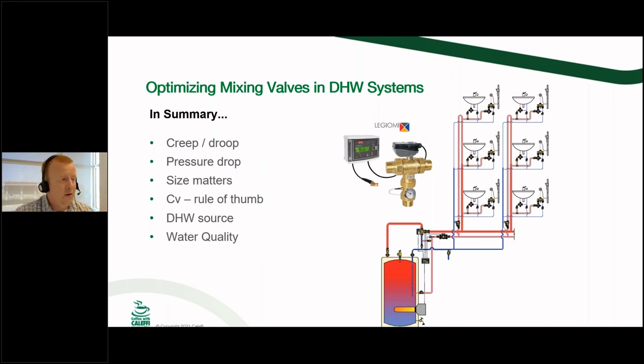But you can take that mixing valve out of the scenario if you've got it isolated. You open the bypass, and you can do the service and maintenance to a mixing valve without having to take down the entire building, which I think is a huge benefit. But you know, again, certain areas may frown upon that. Some areas might okay it, but then you've got to take the valve off, or the handle off the valve. I mean, there's all kinds of things there. So, you know, if you can get away with it, I would be all right with it.